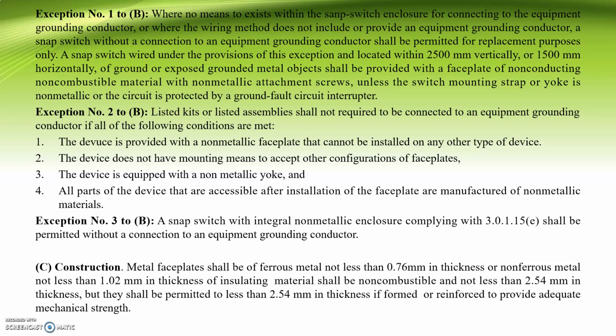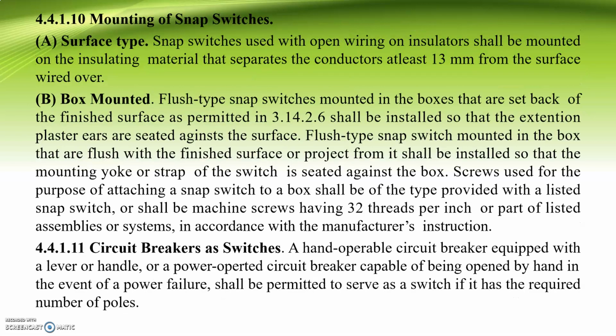So metal faceplates shall be of a ferrous metal not less than 0.76 mm in thickness or non-ferrous metal not less than 1.0 mm in thickness. Faceplates of insulating material shall be non-combustible and not less than 2.54 mm in thickness, but they shall be permitted to be less than 2.54 mm in thickness if formed or reinforced to provide adequate mechanical strength.